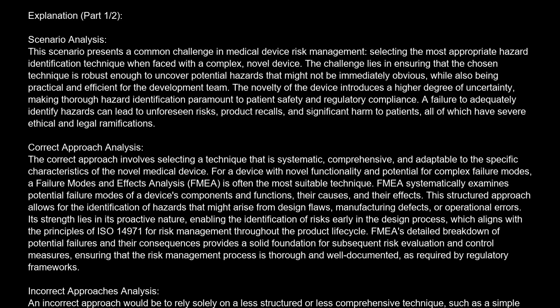For a device with novel functionality and potential for complex failure modes, a failure modes and effects analysis (FMEA) is often the most suitable technique. FMEA systematically examines potential failure modes of a device's components and functions, their causes, and their effects. This structured approach allows for the identification of hazards that might arise from design flaws, manufacturing defects, or operational errors. Its strength lies in its proactive nature, enabling the identification of risks early in the design process, which aligns with the principles of ISO 14971 for risk management throughout the product lifecycle.